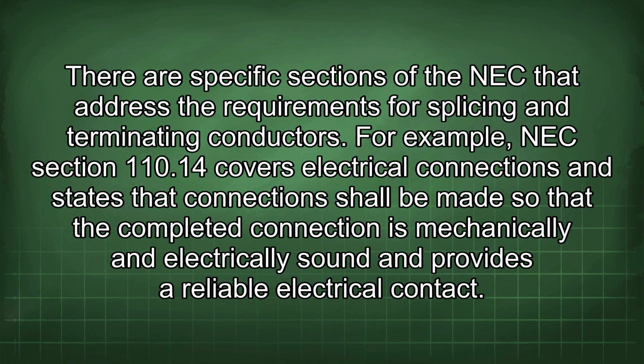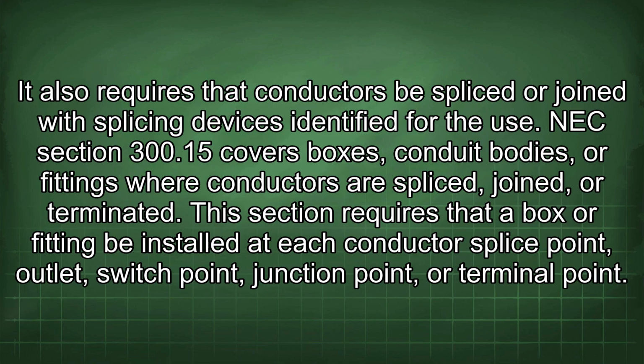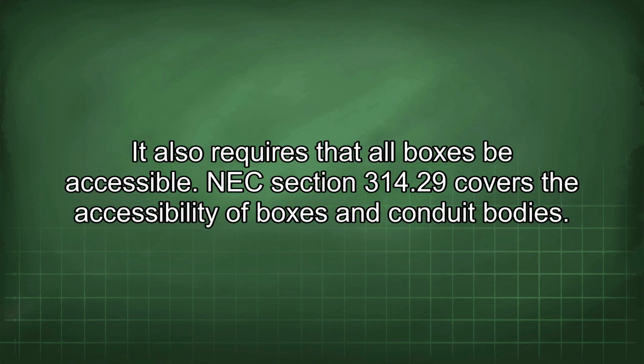There are specific sections of the NEC that address the requirements for splicing and terminating conductors. For example, NEC Section 110.14 covers electrical connections and states that connections shall be made so that the completed connection is mechanically and electrically sound and provides a reliable electrical contact. It also requires that conductors be spliced or joined with splicing devices identified for the use. NEC Section 300.15 covers boxes, conduit bodies, or fittings where conductors are spliced, joined, or terminated. This section requires that a box or fitting be installed at each conductor splice point, outlet, switch point, junction point, or terminal point. It also requires that all boxes be accessible.